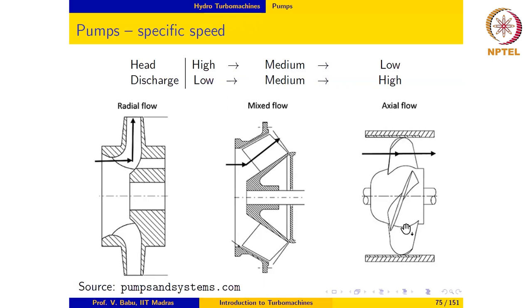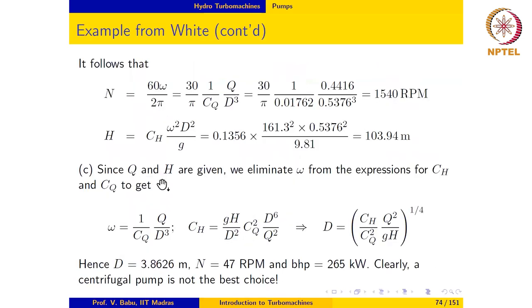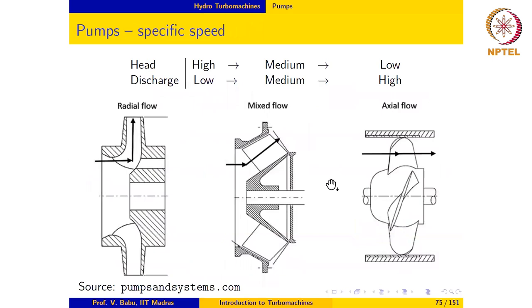If the blade passage is opened further to increase flow rate even more, we end up with an axial flow pump — a purely axial flow machine with no radial component at all. The fluid has only an axial component and a tangential component. The blade passage is quite wide, so it can handle a very high flow rate, but the head developed is not very high. This is ideally suited for low head and high flow rate applications — exactly the sort we are looking for in this case.